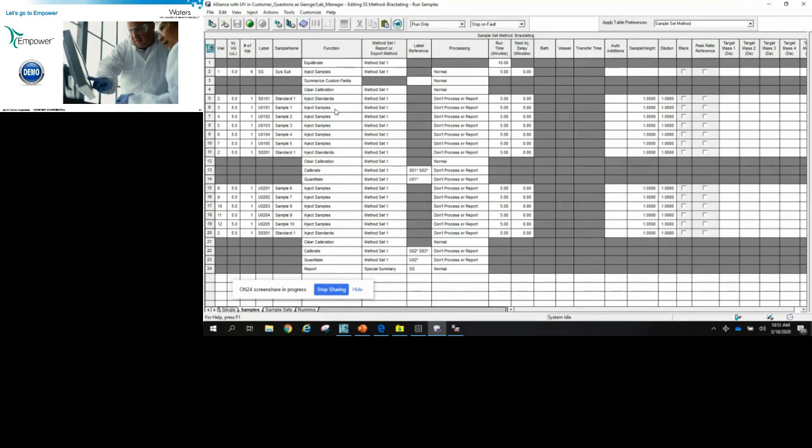We also have inject controls. And inject controls you can think of as a check sample or a check standard. The control would have a known amount of analyte, and when Empower generates the results for the control sample, it treats it as a regular sample. So it looks at the response of the analyte in the control, compares it to the calibration curve, and calculates an amount or a concentration of that analyte, but then it calculates a percent deviation between the calculated amount versus the theoretical amount.